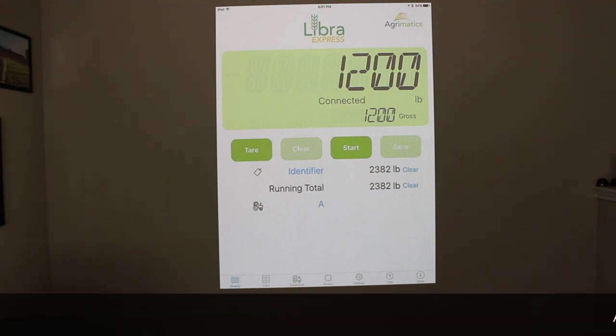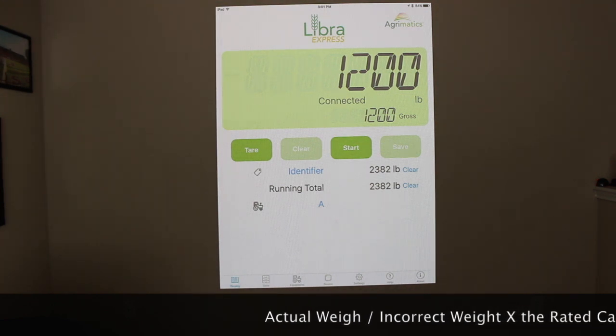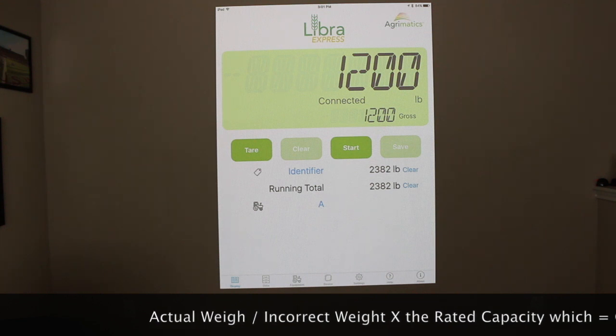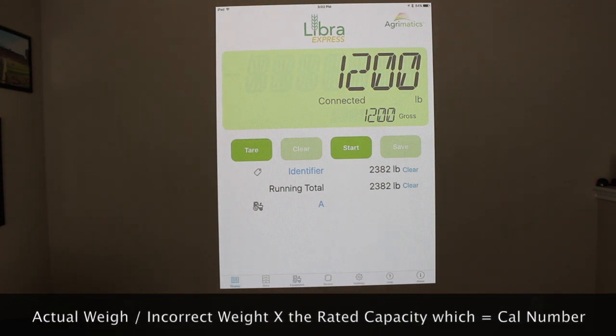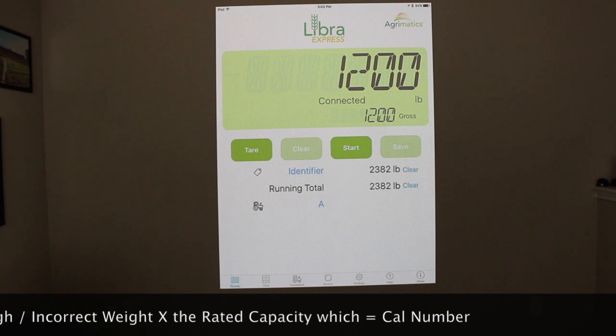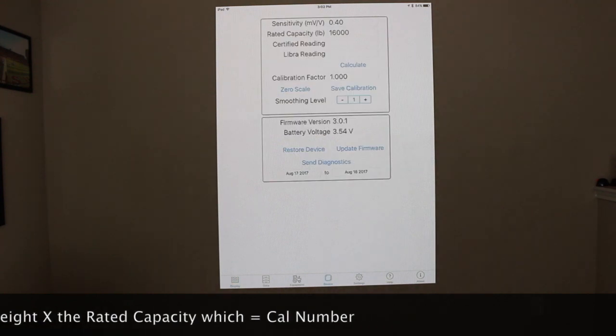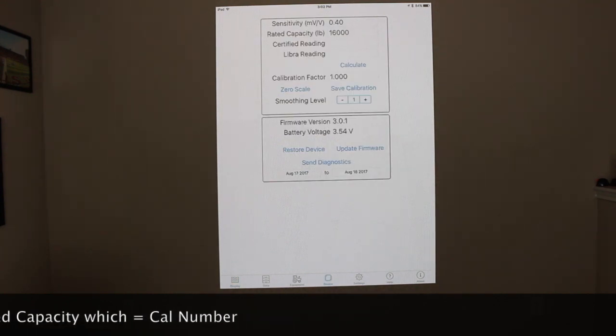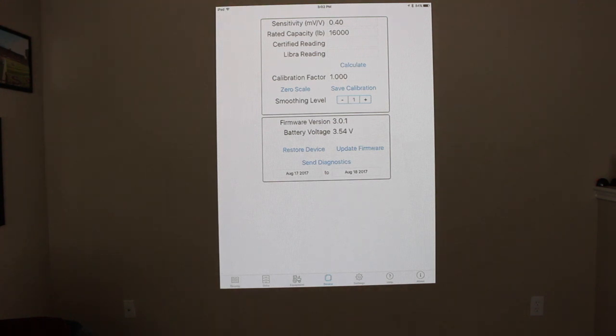There's also a formula that you can use to calibrate. It's taking the actual weight divided by the incorrect weight times the rated capacity. So let's go into our calibration so we can break that down. If we tap on device, you look in there, there's a sensitivity of 0.4. Leave that alone, leave that always at 0.4, and then you can make the calibration process very simple. Another thing to leave alone is the calibration factor. Leave that alone, and then the only thing that needs to be changed is the rated capacity.